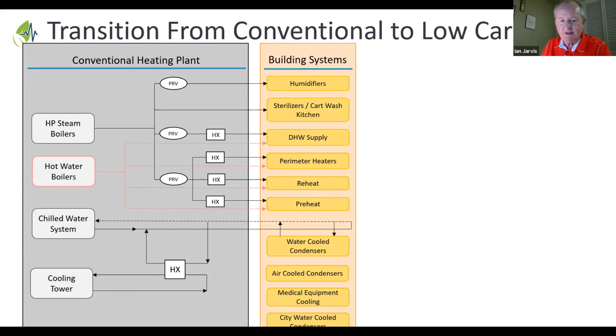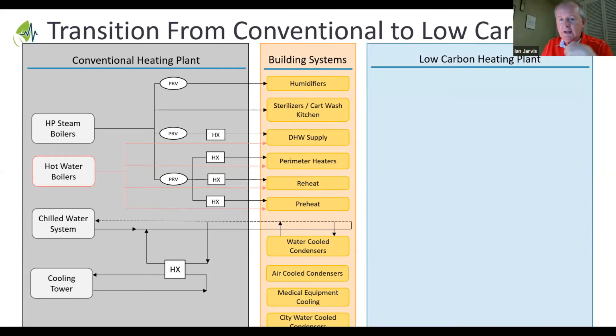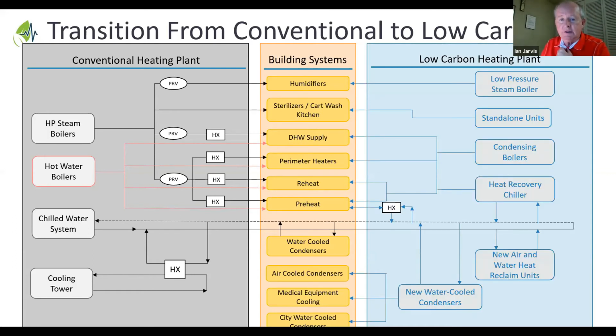The chilled water system very often is picking up the heat from some of those water cooled condensers, one of the case studies we'll be talking about today, but typically rejecting it out through cooling towers or fluid coolers. The rest of those condensers at the bottom are typically air cooled and just blowing the heat out through the roof. When we get to the low carbon heating plant, it looks a whole lot different.